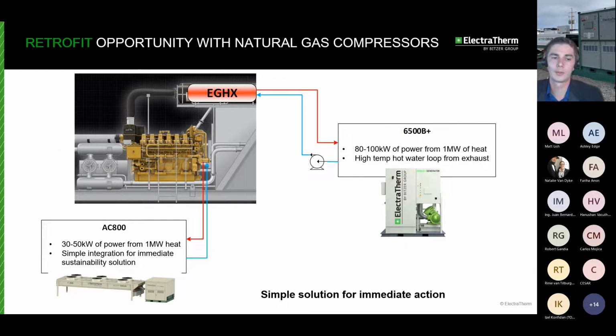So these units are a simple solution for immediate action, and also there's multiple ways to integrate power from waste heat at oil and gas sites. So looking at a typical installation, we can make roughly 30 to 50 kilowatts of power from 1 megawatt of heat in the engine jacket alone using the AC800. We can also utilize that exhaust heat to make a considerable amount of power. When we're looking at exhaust heat, an exhaust gas heat exchanger or heat recovery unit is required. However, we're able to make a lot more power because we're using a higher temperature from that exhaust, so we're exploiting more of a difference between our heat source and the ambient conditions.